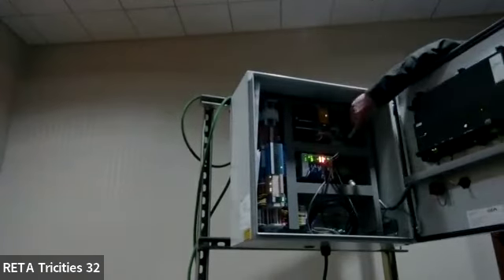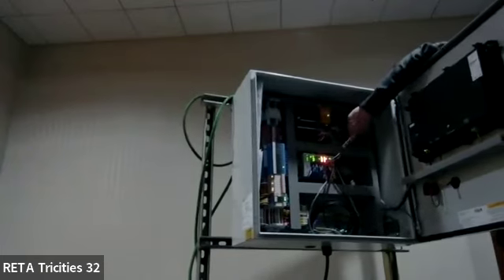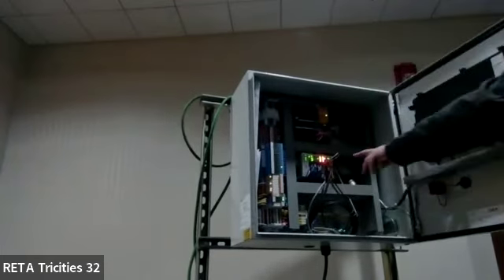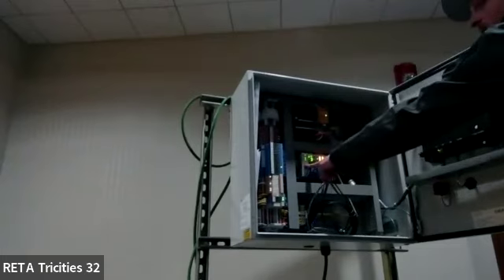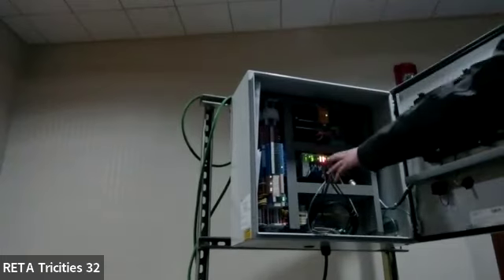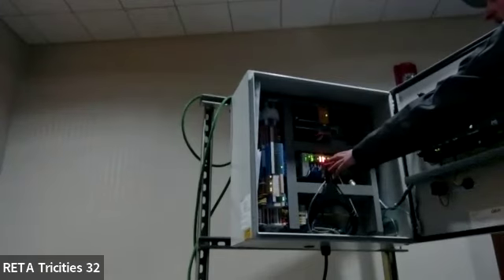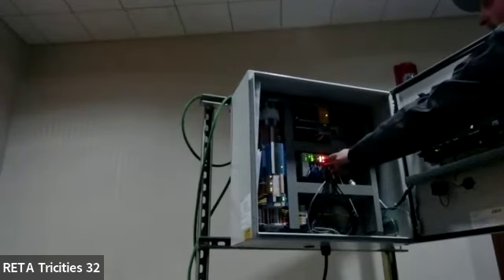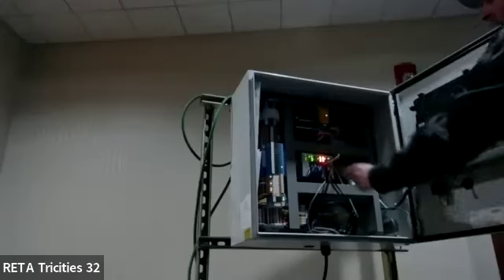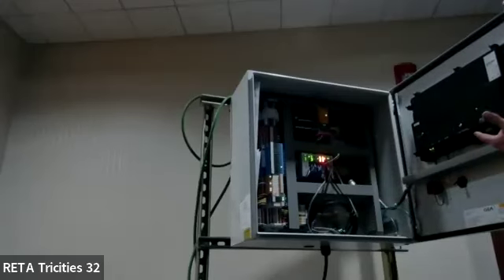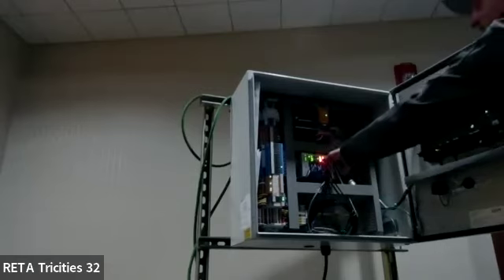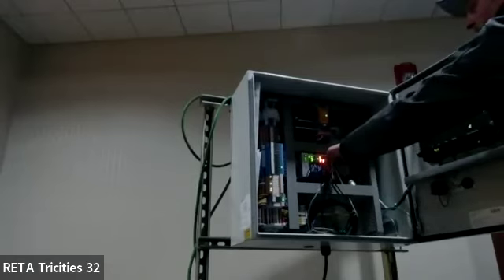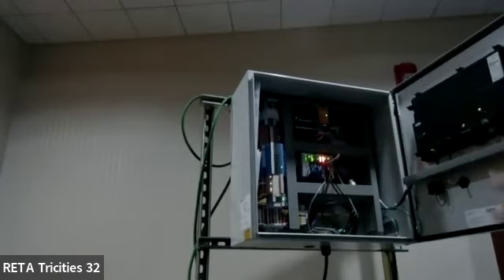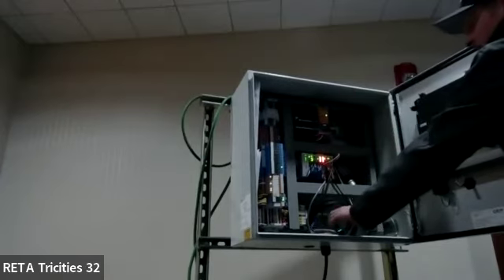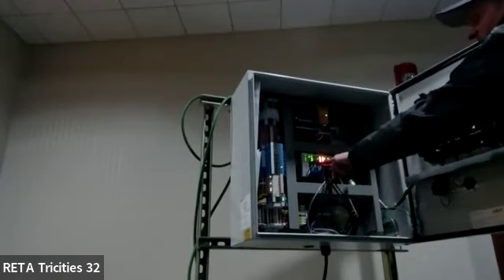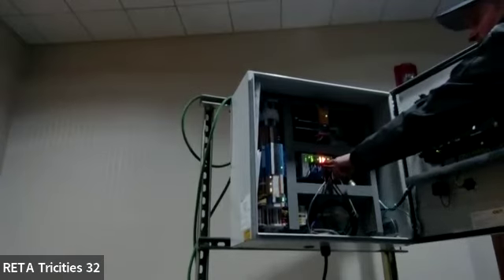Yeah, so this is the PLC. Right here, these are all the slices. You've got the bus coupler, the main motherboard to all these PLC slices. You've got red and green lights on here. Right now, we only have a suction temperature probe and a suction pressure transducer wired in. That's the only two that are going to show that they're getting a signal. We also have a potentiometer wired in, which is showing down here that it's getting a signal.